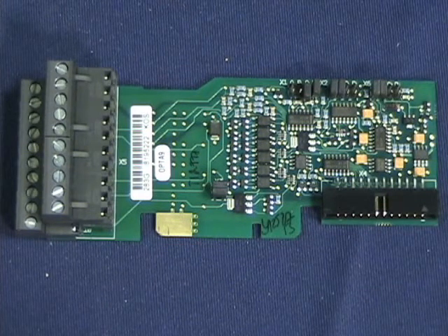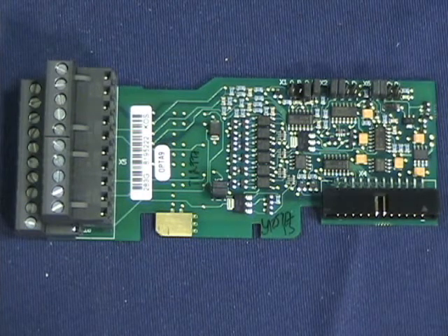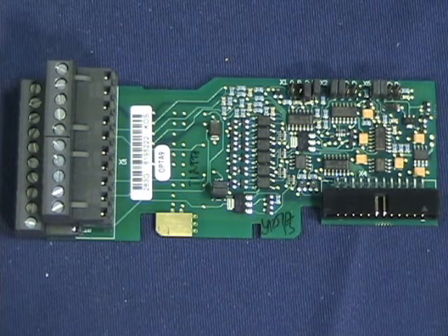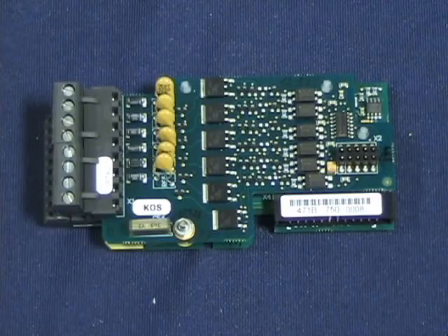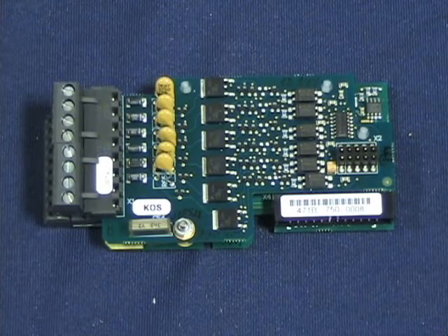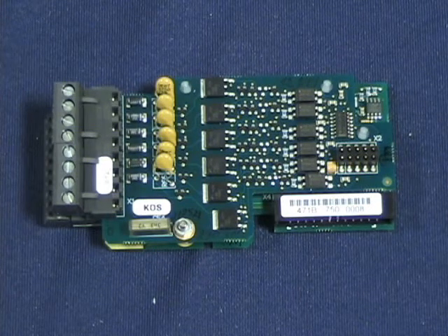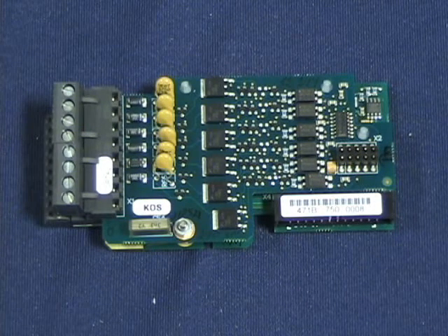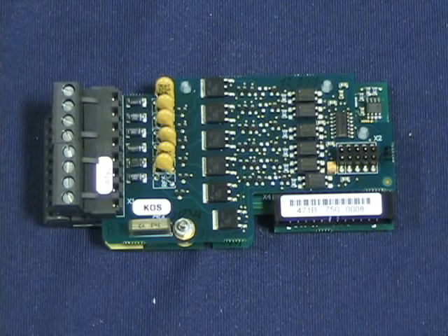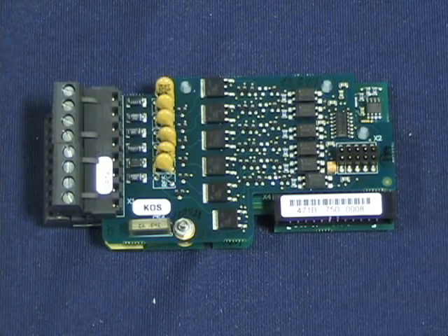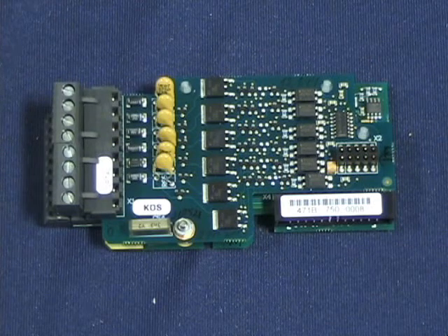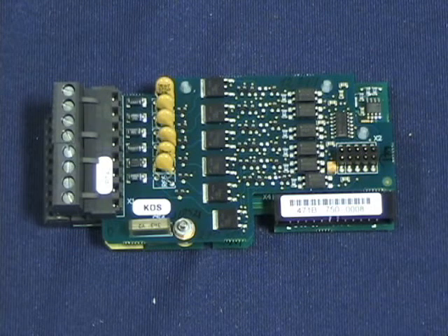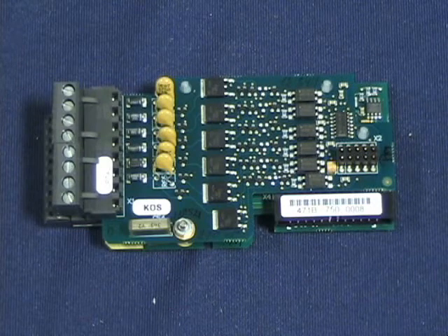The OPT-A9 card is the most common I/O card distributed with the ACCel500, but there are other options for slot A. The OPT-AL card is one alternative for slot A. This card has 6 digital AC inputs, 2 analog inputs, 2 analog outputs, and 1 open collector digital output.